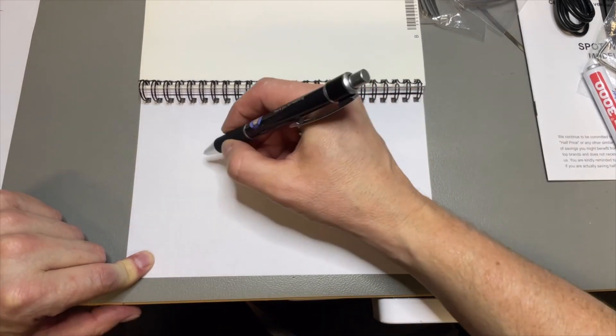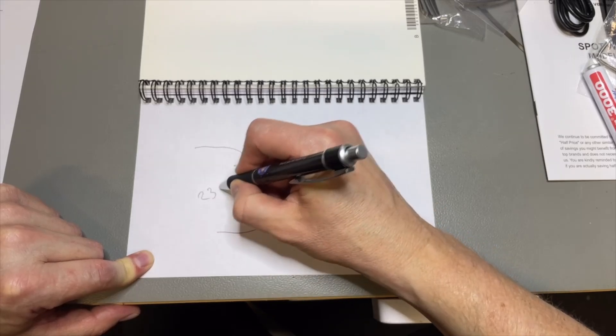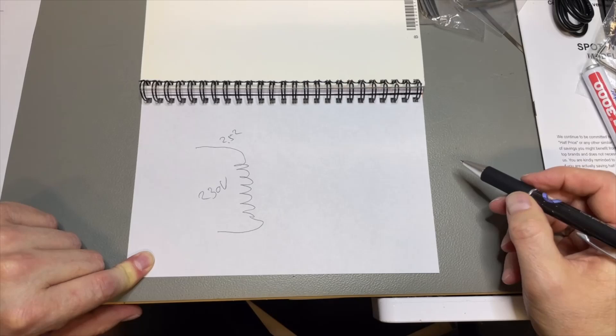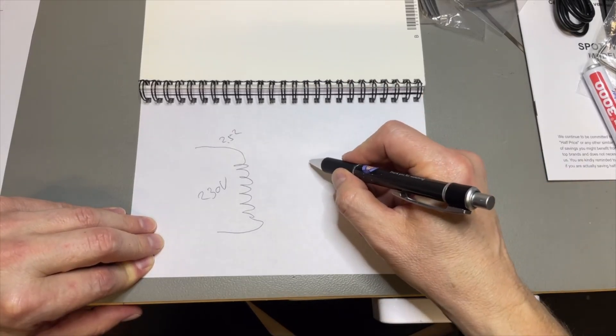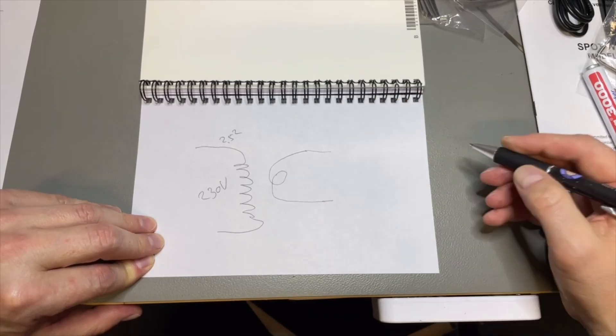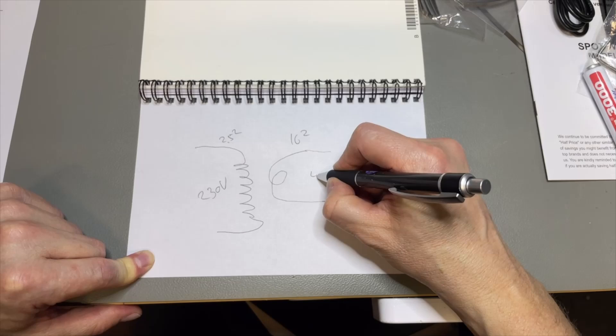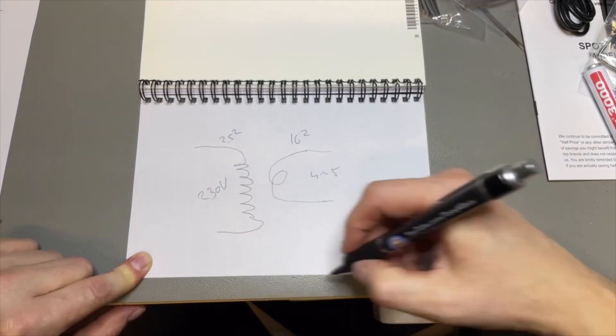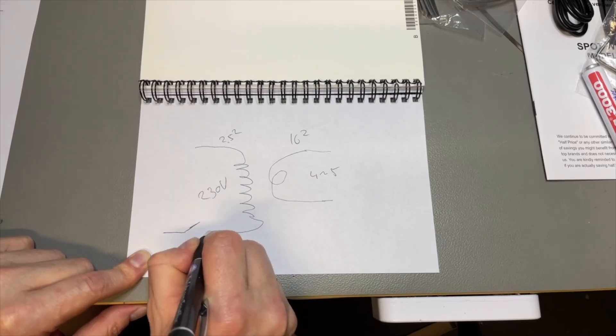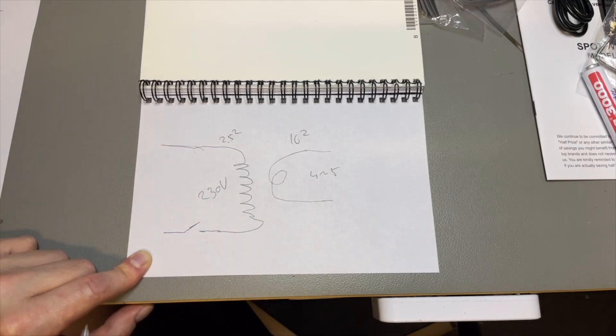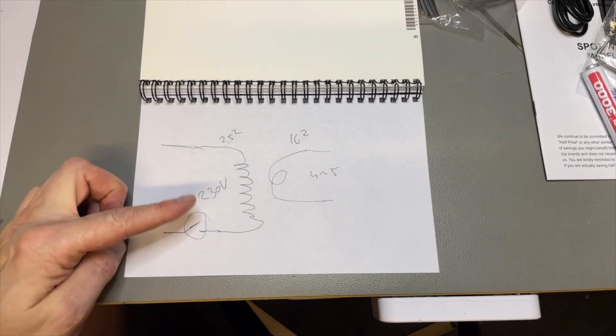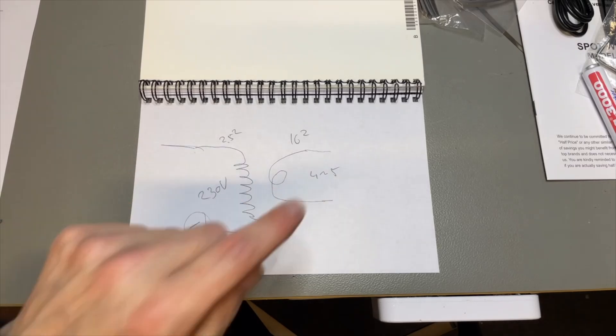If you wonder how this works - how are we able to pulse 800 amps? They do this with a transformer. The voltage secondary is very low. A lot of windings on the primary side, probably 2.5 square. On the other side we have just one or two windings, and these cables are crazy big, maybe 10 square or more. It's just two or three windings, between 4 and 5 volts. Then the switching we do on this side with a triac and some electronics. You pulse on this side at 15-16 amps, and then you're switching 800 amps. Let's open it and have a look inside.